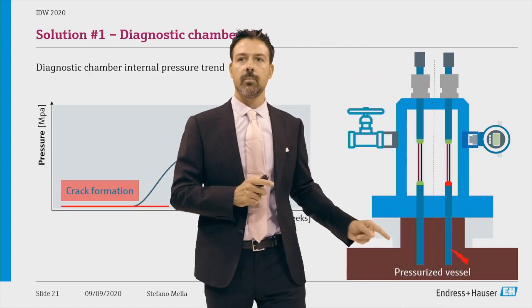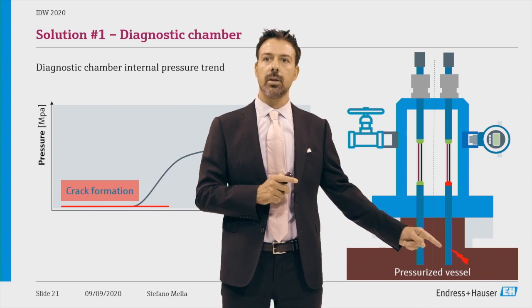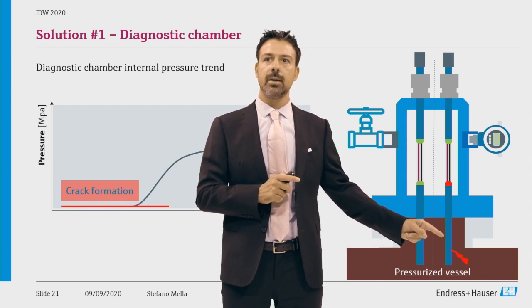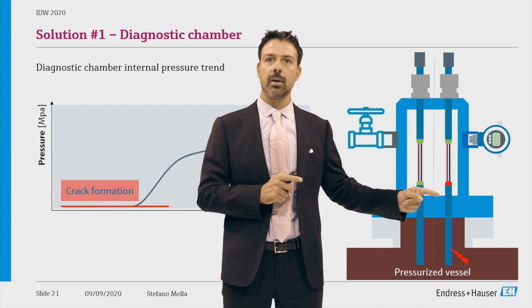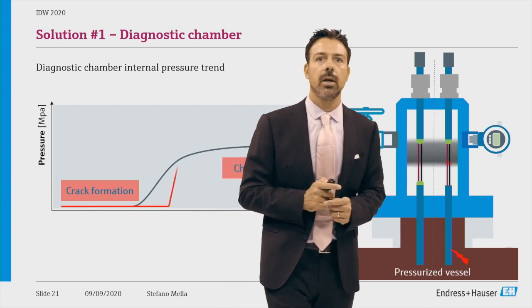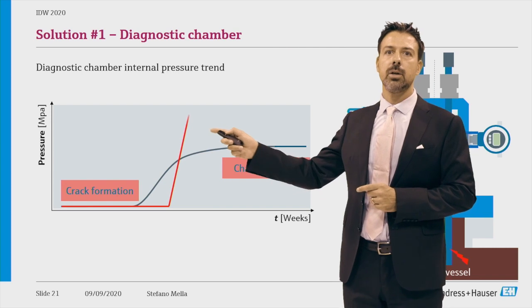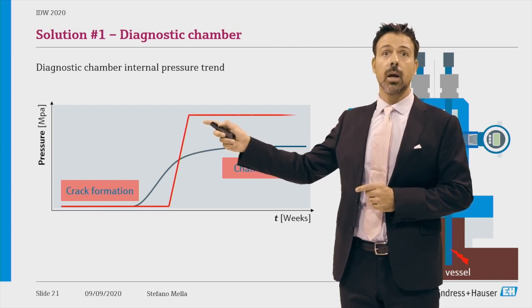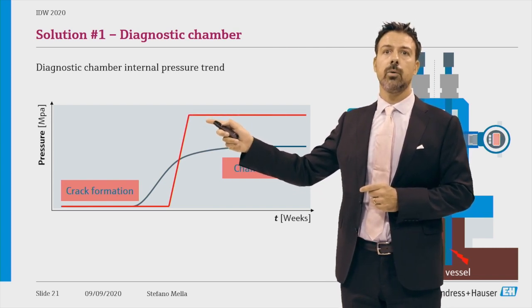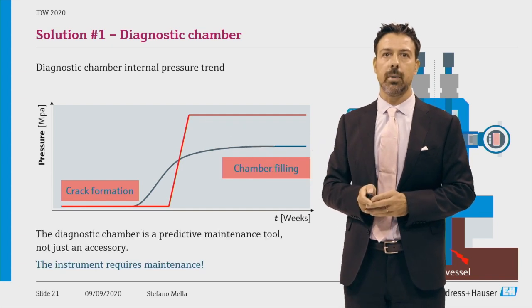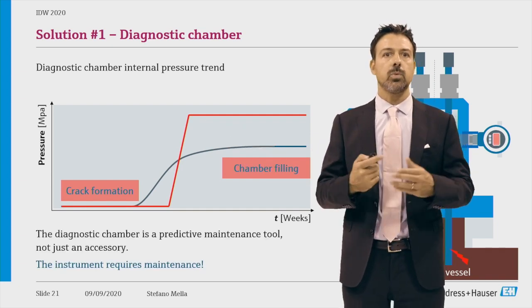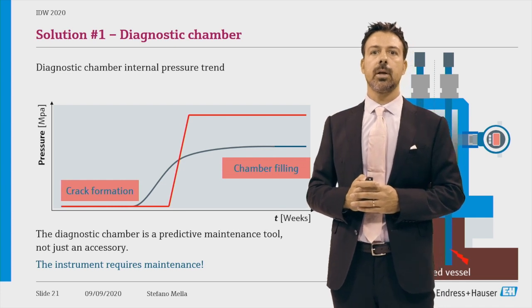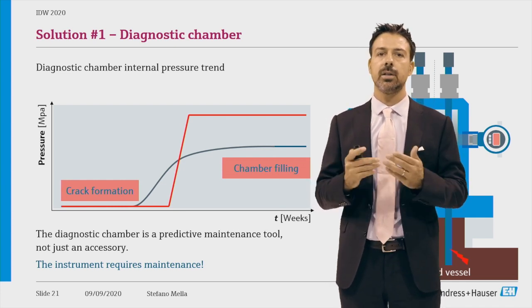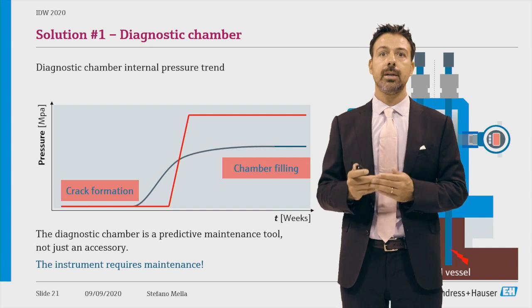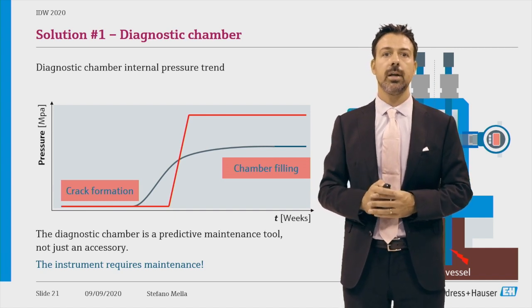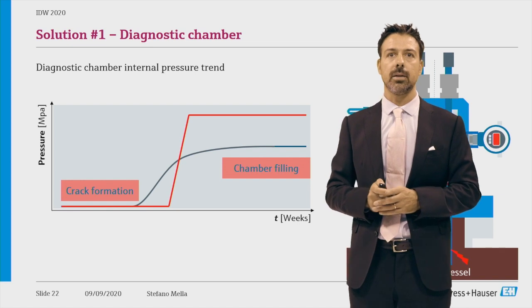Differently, when we have a crack on the thermocouple, then it's again a matter of time and the pressure will increase in the diagnostic chamber. How much? For sure, much more than before. And the pressure this time will reach the operating pressure of the plant. So that's why the diagnostic chamber is a predictive maintenance tool and it's not just an accessory. And this trend shows clearly that the instrument needs maintenance.